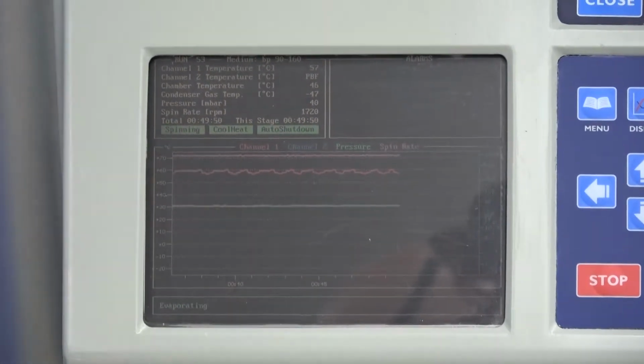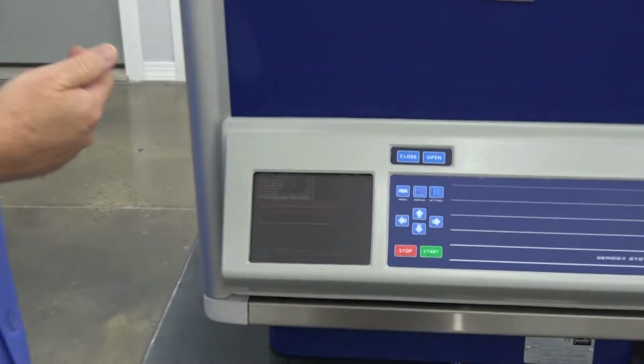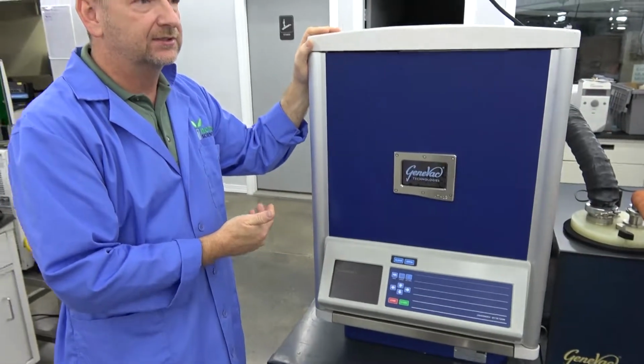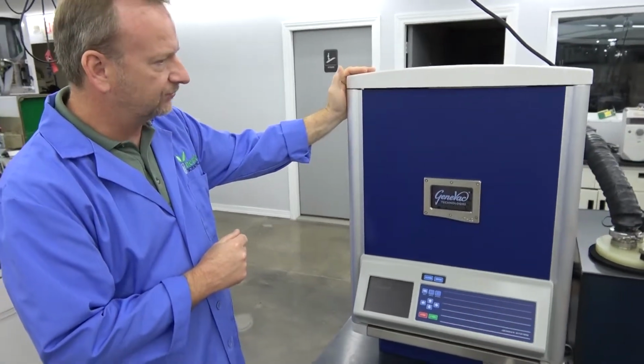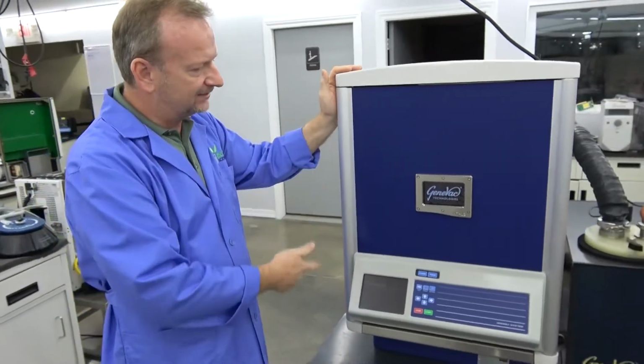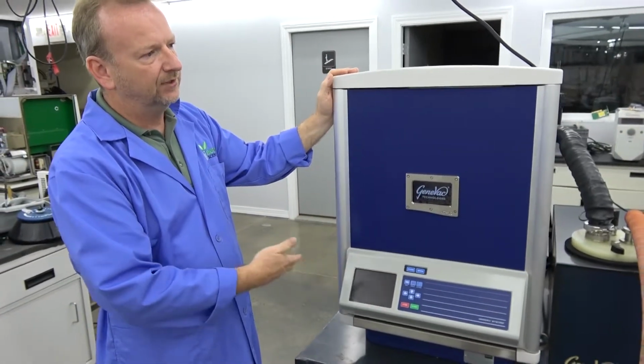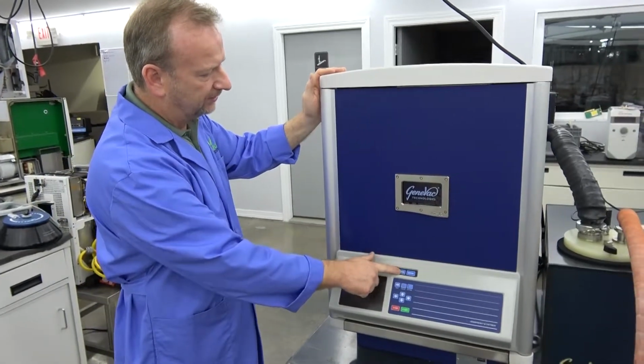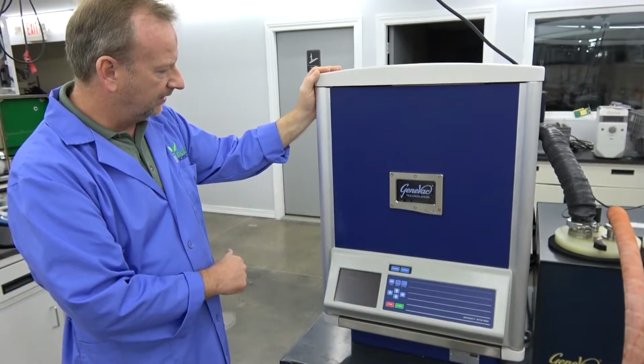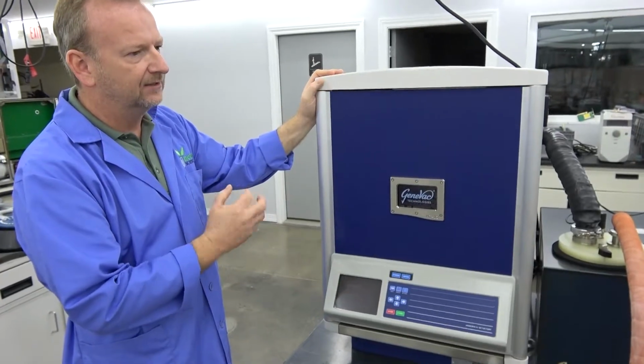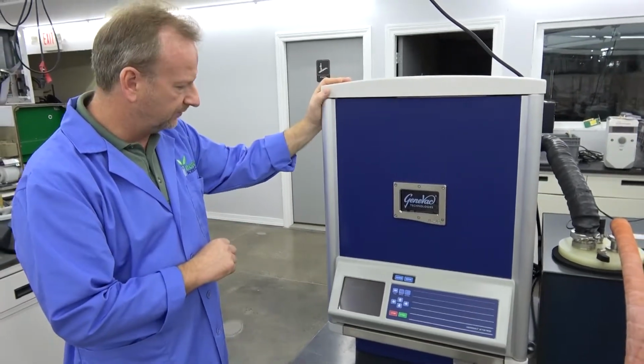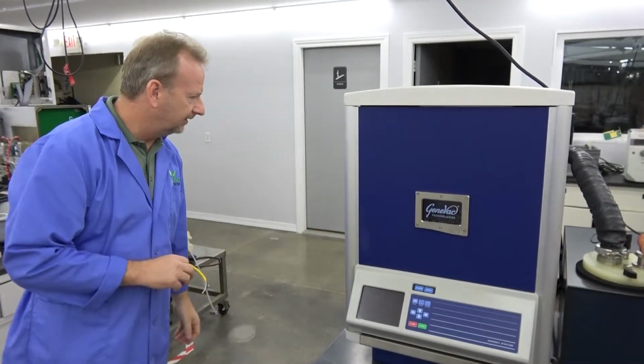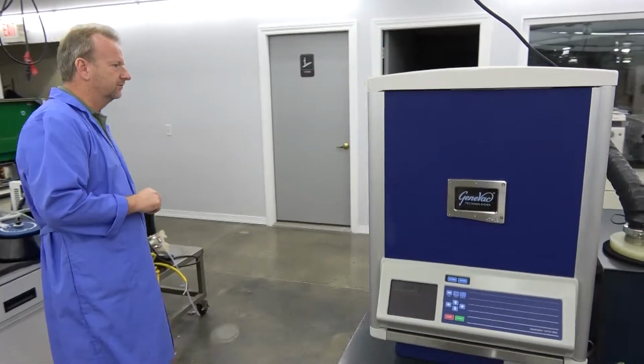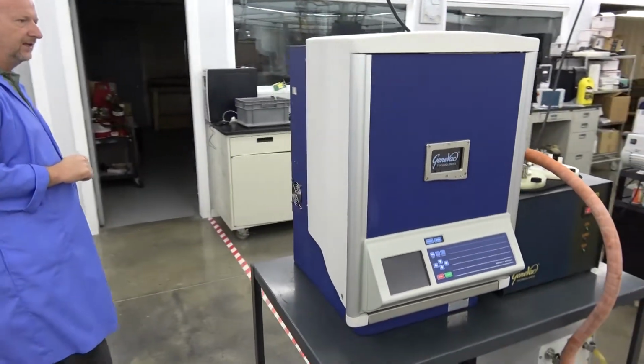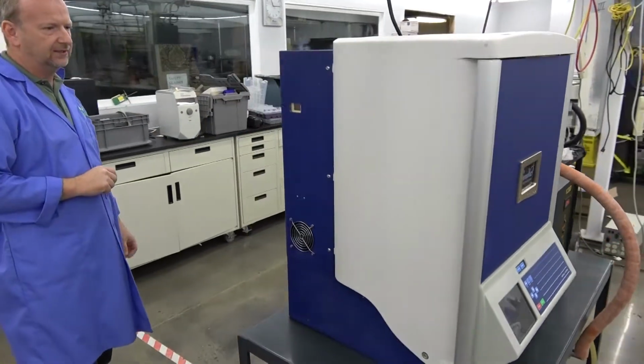Also, underneath there's a belt that runs the spinning centrifuge part, and I replaced the belt because it looked a little old and worn, so I wanted to make sure that was up to par. I greased the latches on the door, and greased some of the components, because it has the automated open and shut option, and everything just needed grease, so it works really smooth now. But we'll do a walk around of the machine here. Really nice system. A couple little odds and ends just to do the maintenance on.